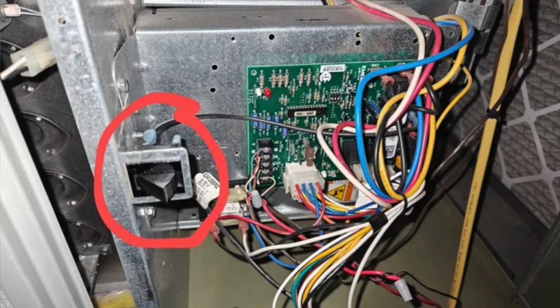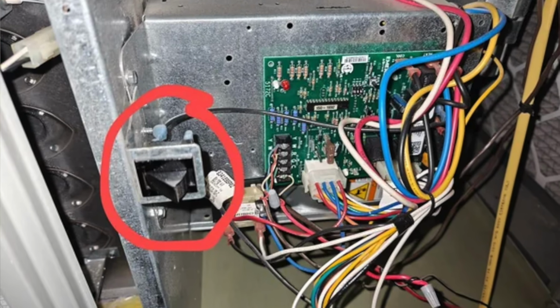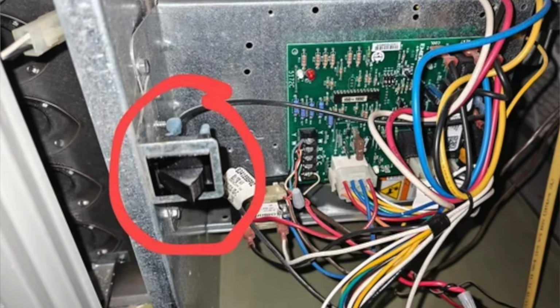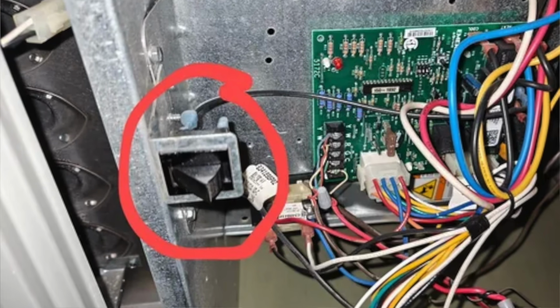So if you've now reset the power... I remember years ago having a customer call us saying, hey, I don't have AC, and when I got there it'd be running fine. I wasn't able to catch the problem in action. I would sometimes train my employees not to take covers off - you need to try to diagnose that system, because with some systems, as soon as you pull that cover off, if it has a door switch, it will clear that issue, and now you've missed the opportunity to, for example, count the blinks on the LED that tells you what's wrong with the system.